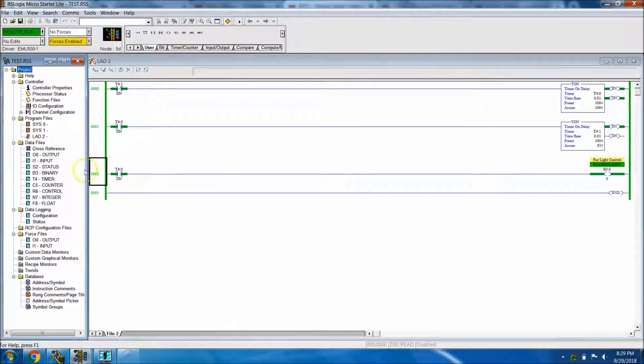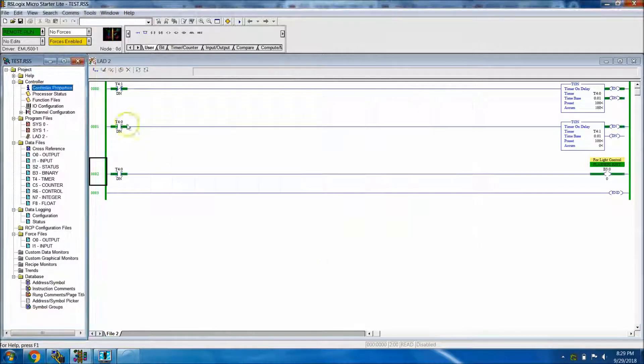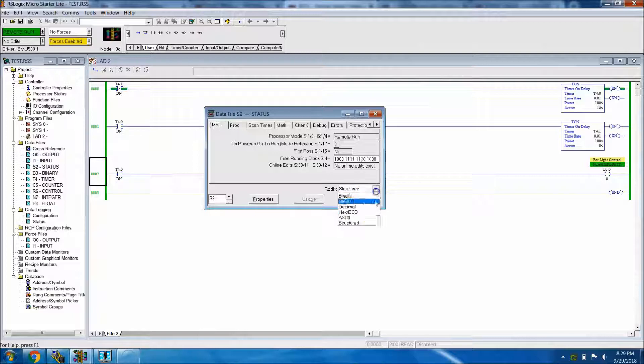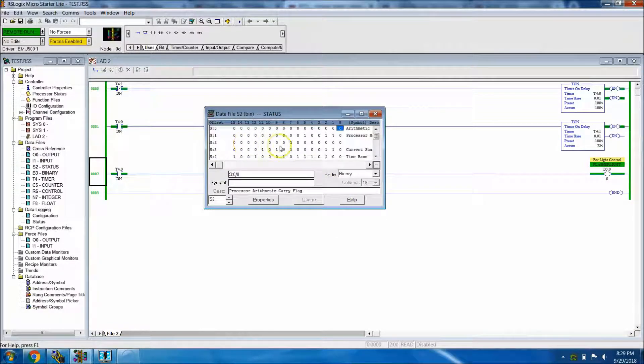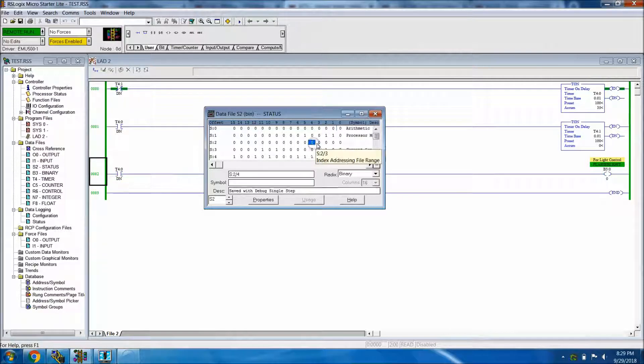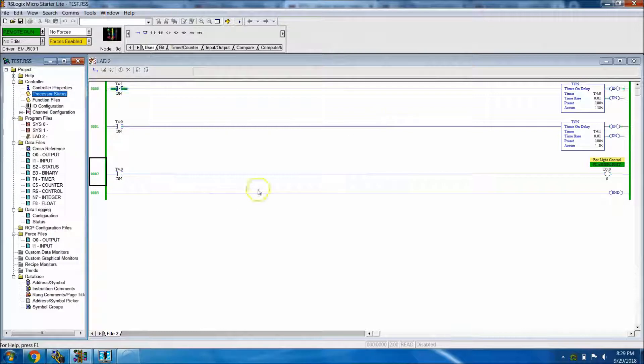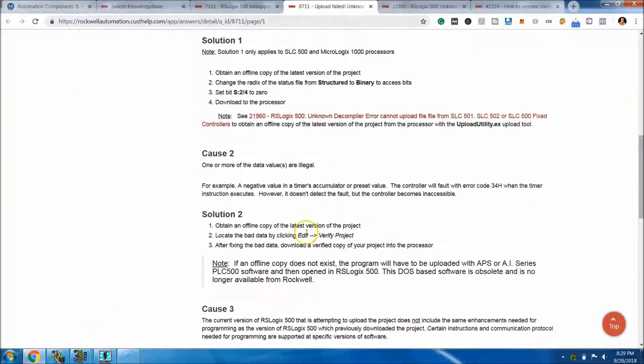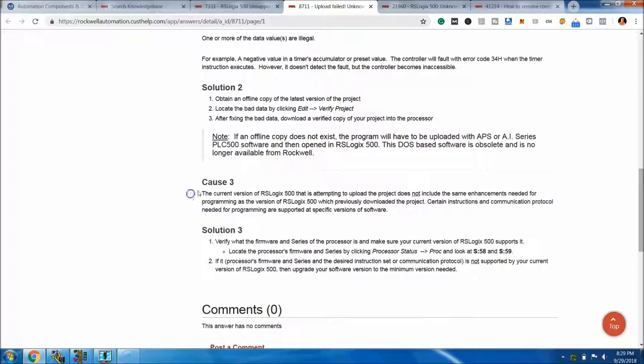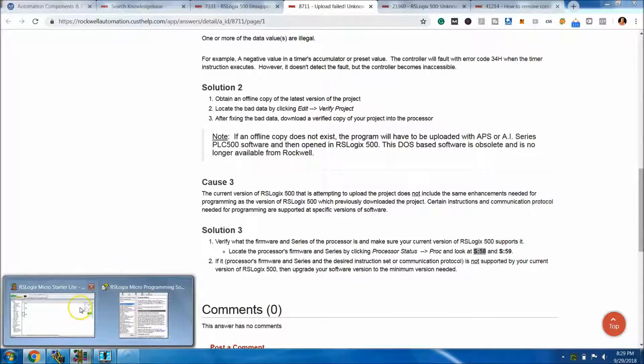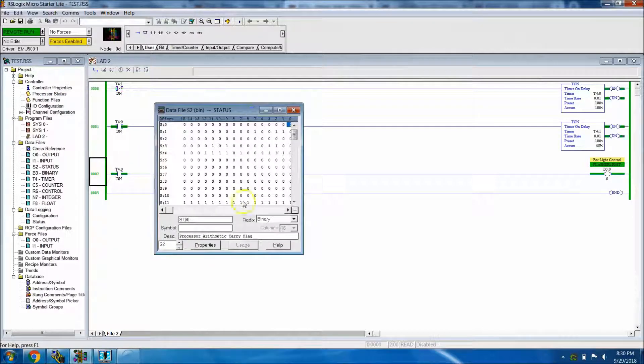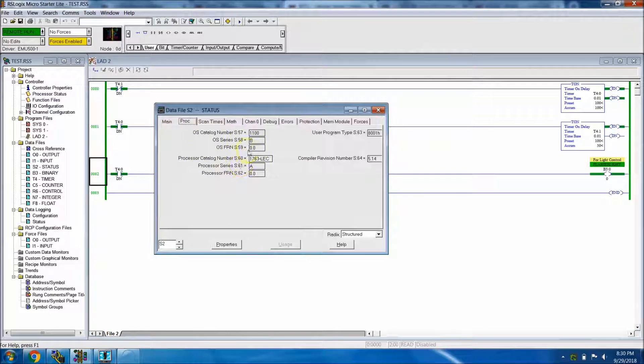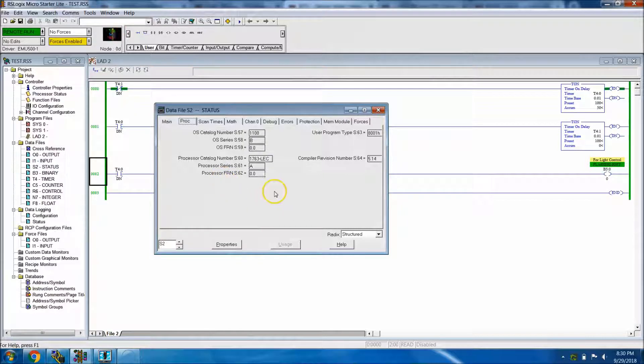That is easily obtained by going to the processor status and then changing the radix to binary. You're going to look at S:24. I'm online, so if S:24 or S:23, either one of these are set to one, then you need to change it to zero. After all that's checked and that's good, I would definitely verify this as well: verify that you are running the correct firmware and versions. You can check that by looking at S:58 and S:59 by going to processor status, changing it back to structure, and then looking at exactly what versions and everything that you're running.